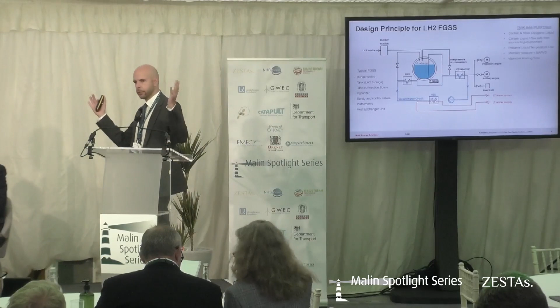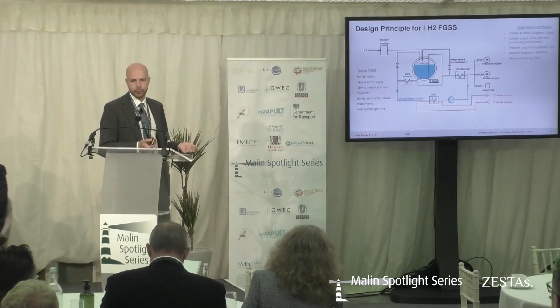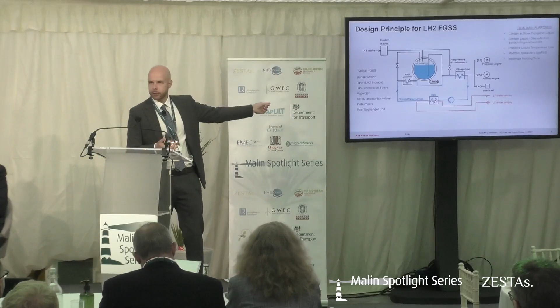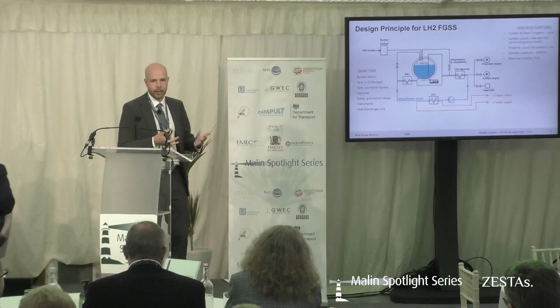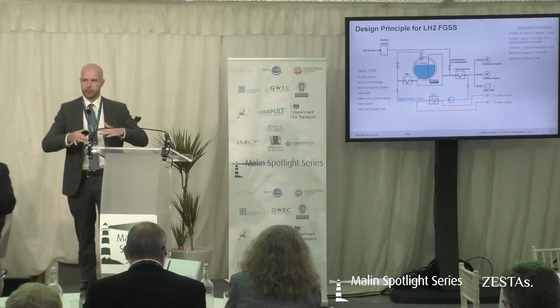What happens now when we take liquid out of the tank? Then the internal pressure of the tank will slowly decrease. To prevent this, we have an additional vaporizer circuit called the pressure buildup unit, also working with vaporization. We take liquid out of the bottom of the tank, send it through this pressure buildup unit, vaporize it, and send the gas back on top to prevent the pressure loss inside the tank. So we can always control the pressure. And if the pressure under any circumstance would be too high, we can take gas directly from the top of the tank, just send it through the vaporizer, just heat it up. So there's always a way to control your pressure, which is the driving force behind this process.